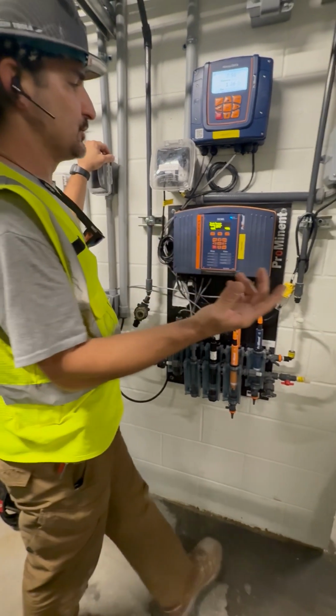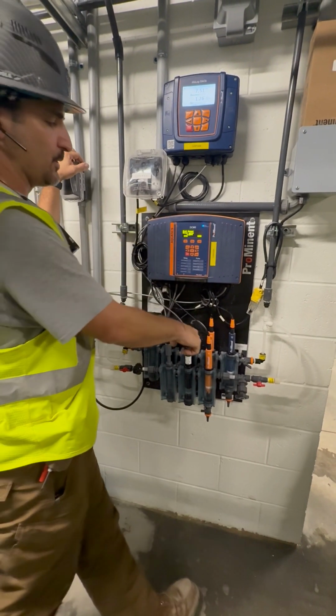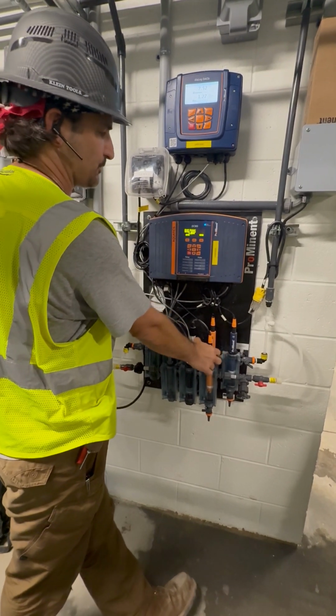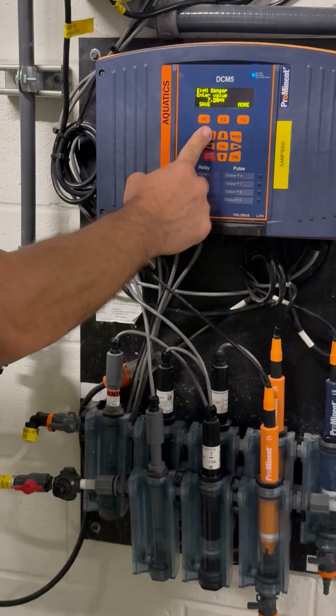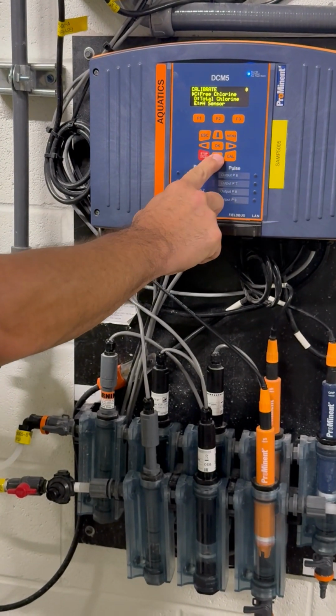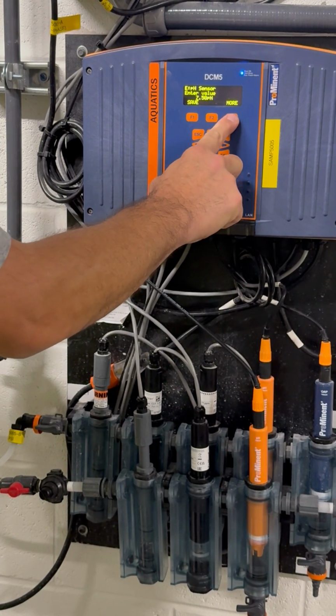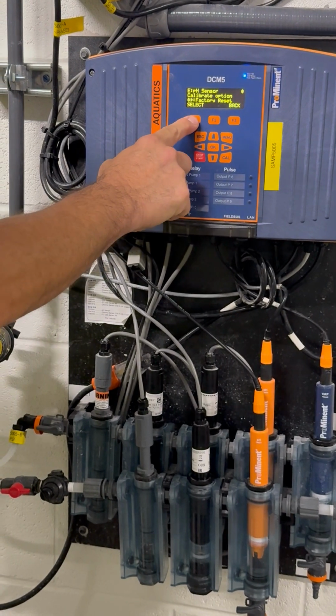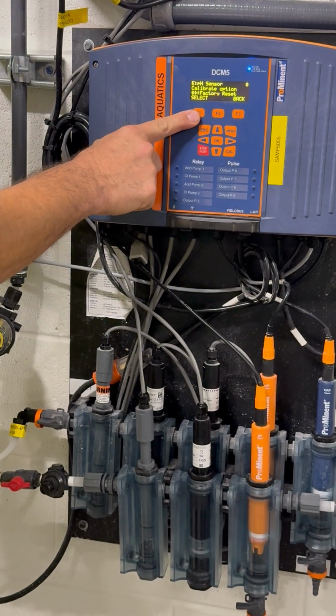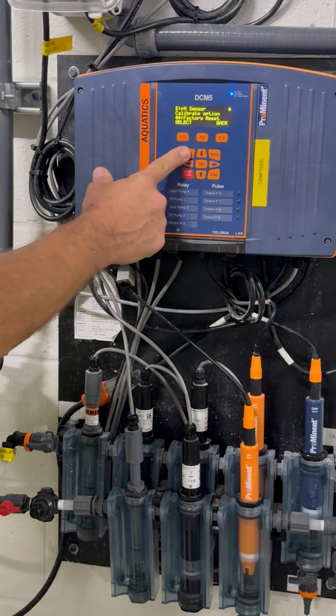When we do that, we clean our probe, or we do a probe replacement. You're going to hit the calibrate button, go to pH, hit more, and then select factory reset. That's how you get that 0 back.